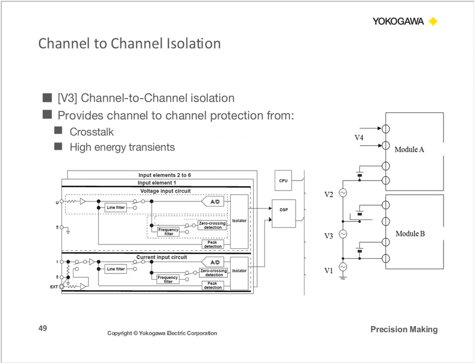The third type is channel-to-channel isolation. Again, this protects you from crosstalk, so noise bleeding from channel to channel. It also prevents high energy transients from damaging the entire module. So let's say you expose channel 1 to too much voltage. Well, your channel 2 is going to be protected, and you will still find that it's accessible to make measurements.